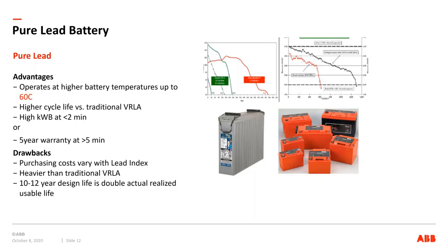They are based on pure lead, so it's the fact that they are based on pure lead that gives generally overall better quality of the material that's used in the battery, and then the plates are thinner. So typically for the same size battery, there will be between 50 and 70% more plate in the battery, so more surface area, which means better performance for the battery. We are seeing them.